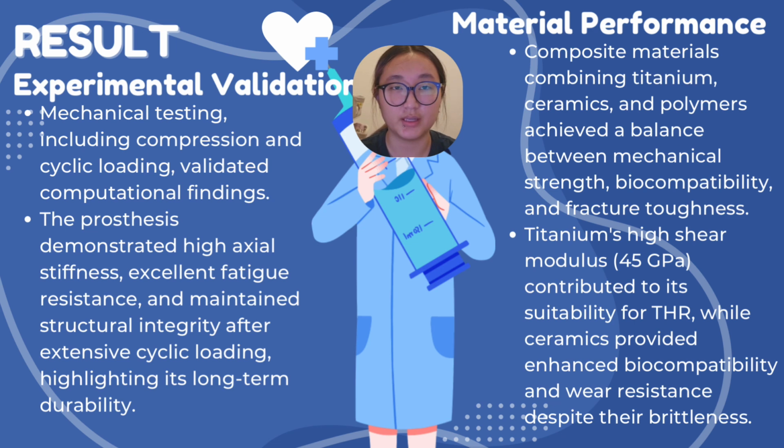Experimental validation. Mechanical testing, including compression and cyclic loading, validated computational findings. The prosthesis demonstrated higher axial stiffness, excellent fatigue resistance, and maintained structural integrity after extensive cyclic loading, highlighting its long-term durability.